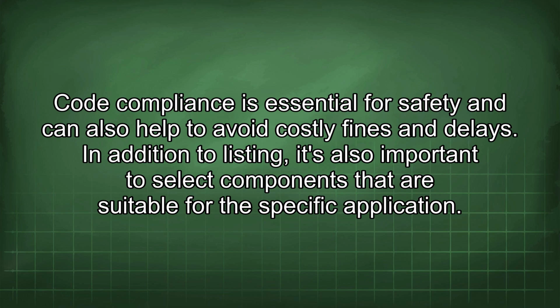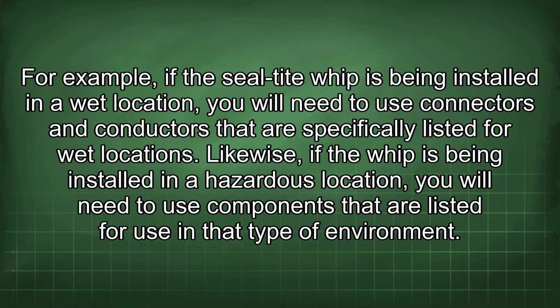In addition to listing, it's also important to select components that are suitable for the specific application. For example, if the Seal-Tite whip is being installed in a wet location, you will need to use connectors and conductors that are specifically listed for wet locations. Likewise, if the whip is being installed in a hazardous location, you will need to use components that are listed for use in that type of environment.